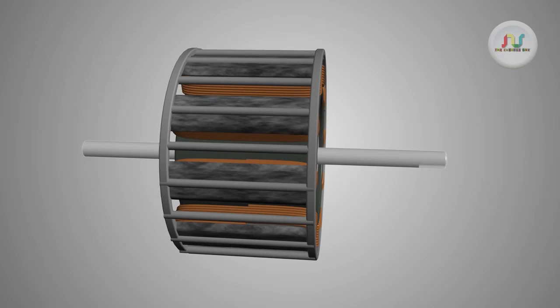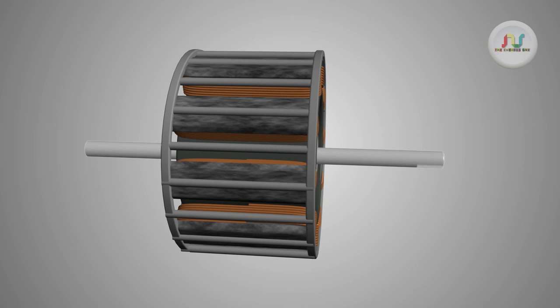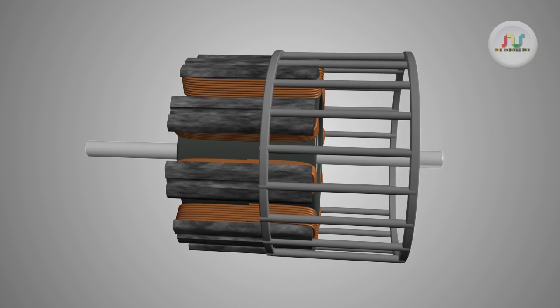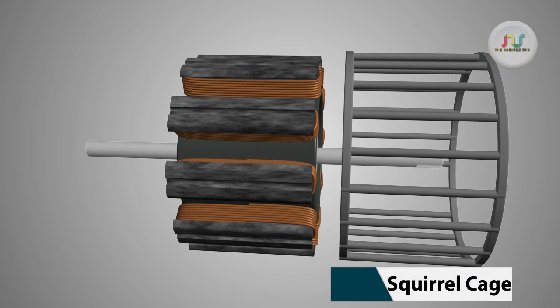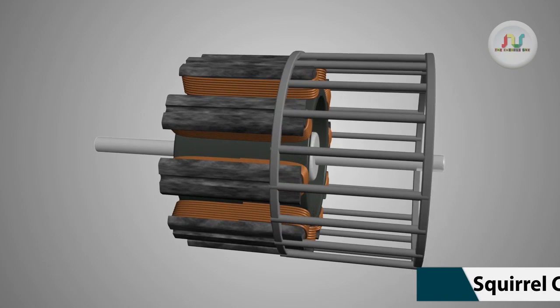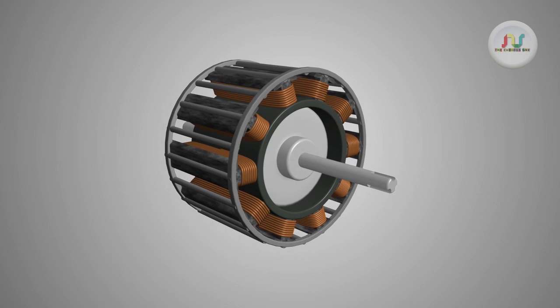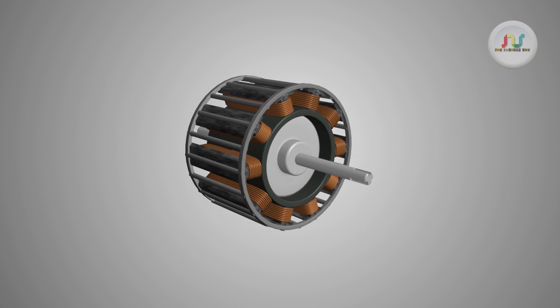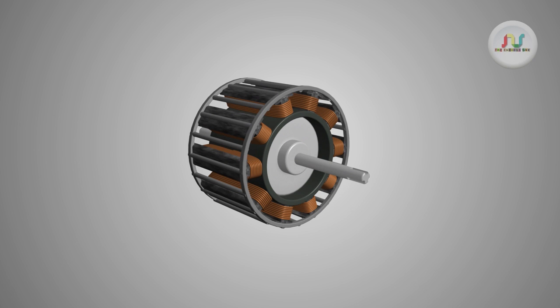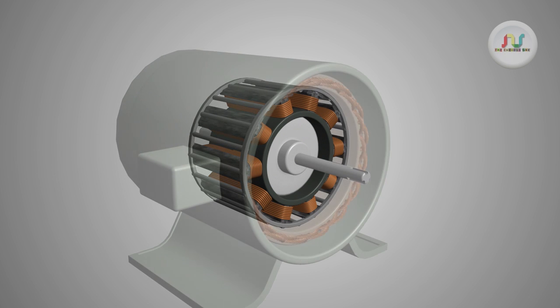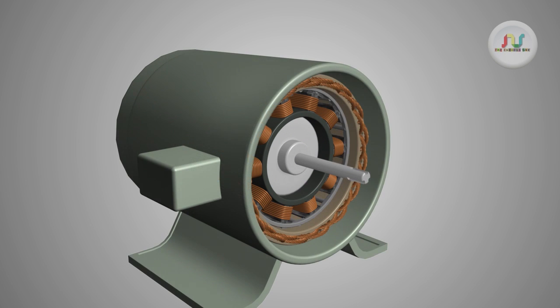To make synchronous motor self-starting, a squirrel cage arrangement is cleverly fitted through the pole tip. At starting, rotor field coils are not energized, so revolving magnetic field induces electricity in squirrel cage bars, and the rotor starts rotating just like an induction motor.